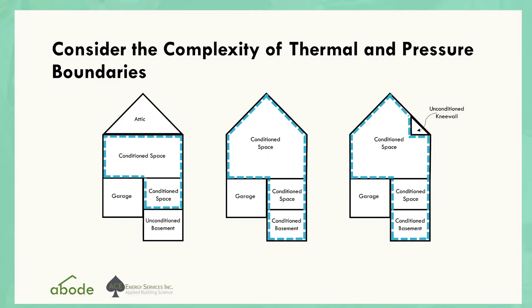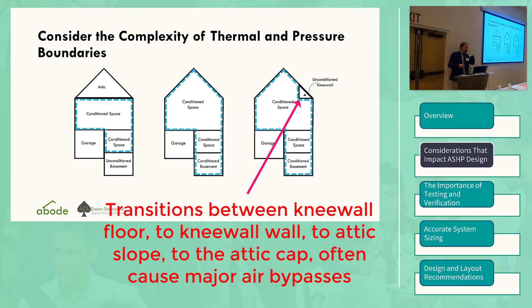Probably the trickiest one is the roof. You either do the whole roof deck, all the way down to the eave, or you've got an unconditioned space over here, behind a knee wall kind of thing. We work with builders for a long time, and it's still hard to get this down with some of them: it's got to be continuous. Pay attention to this detail, because it could be a thermal bypass, which could dramatically raise the air exchange rate of your home. You'd not only fail to meet code, you'd have a different heating and cooling load for an air source heat pump system.